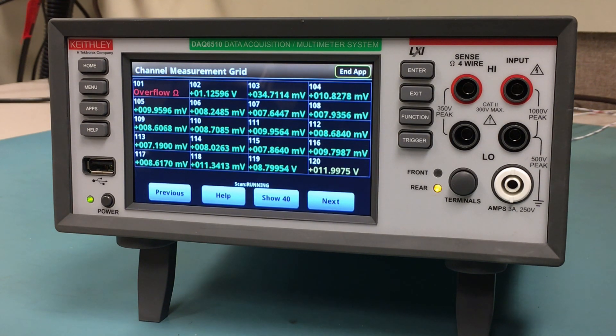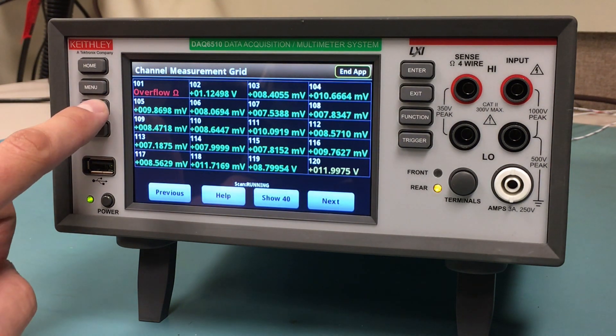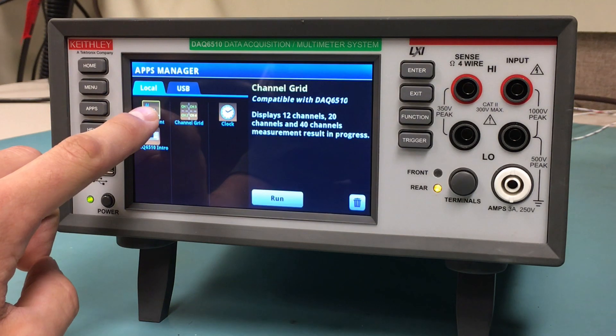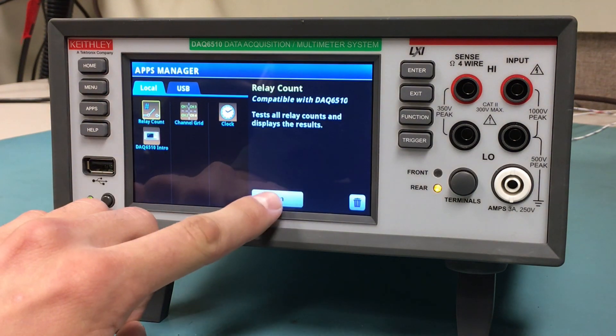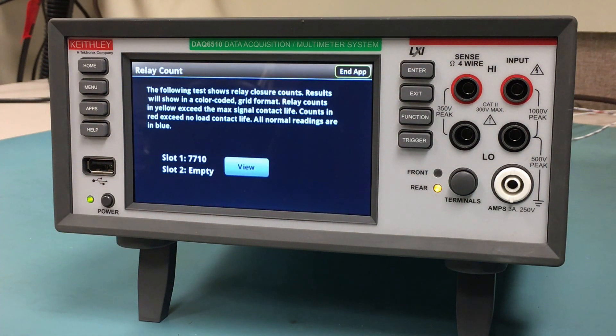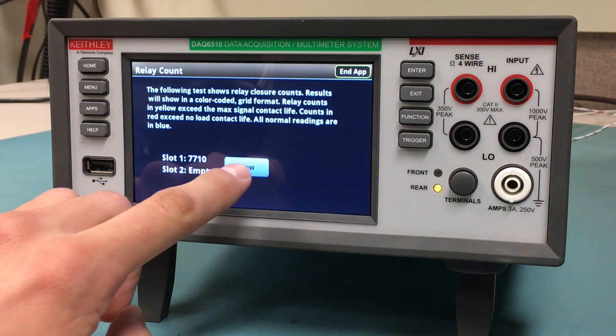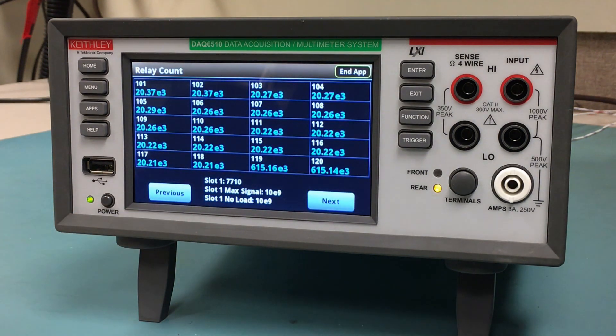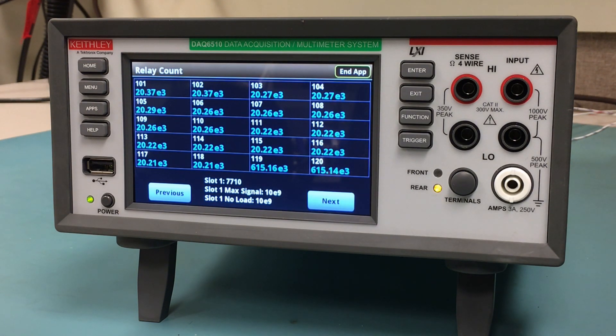If we believed this overflow to be the result of a faulty relay on the card, we could switch over to the Relay Count app by pressing the Apps key and running the Relay Count app. Press View to see the Relay Closure Counts. As you can see, all of the Relay Closure Counts are displayed in blue, meaning they're all within spec.